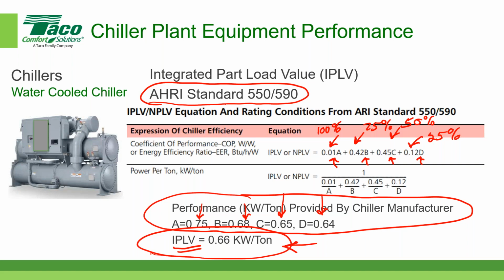There is another value which is somewhat highlighted here. It's called the non-standard part load value, and that's what the N stands for, non-standard. So the IPLV is based on the standard, and the N is the non-standard. So the non-standard is customized for your chiller plant installation or design. So that's the difference between the IPLV and the NPLV. That's very clear.